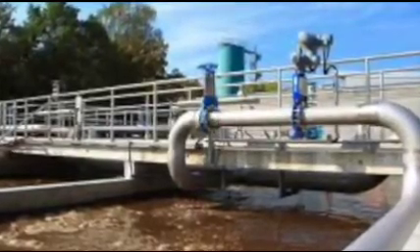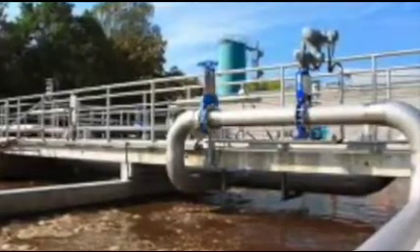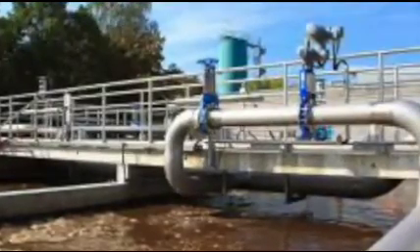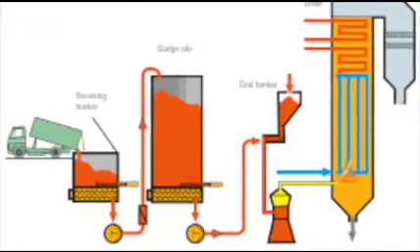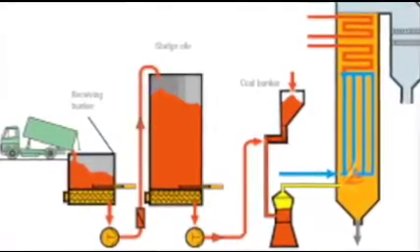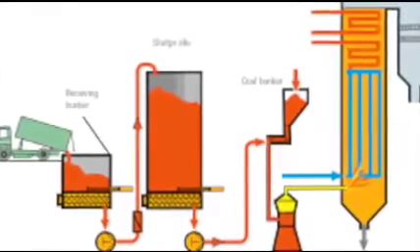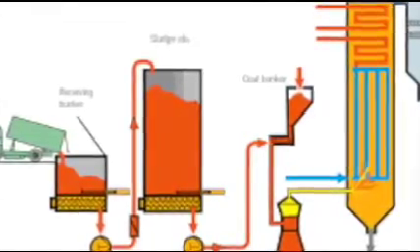The sludge collected from the settling tanks is put into a digester tank to reduce its mass, and then it is further processed to remove water. Methane is collected from these tanks and can be used as fuel. The digested sludge is then used as fertilizer on farms, moved to landfill, or even burned.